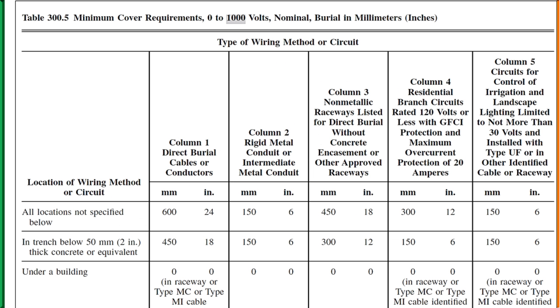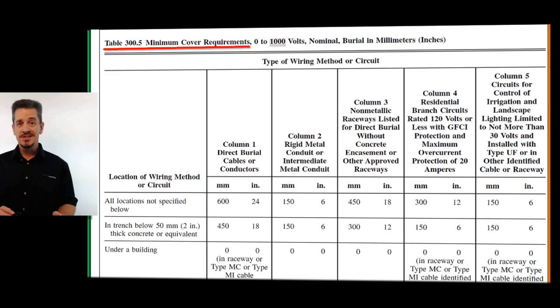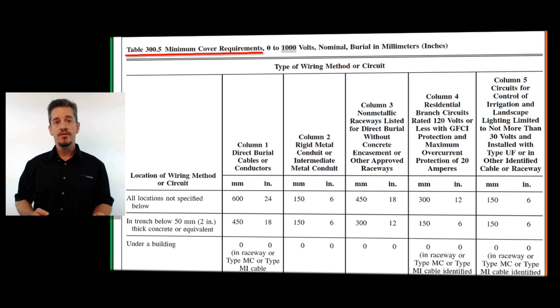When we go to that table, look at what this table is for. This is for our minimum cover requirements. This is not burial depth. There is a difference between cover requirements and burial depth.